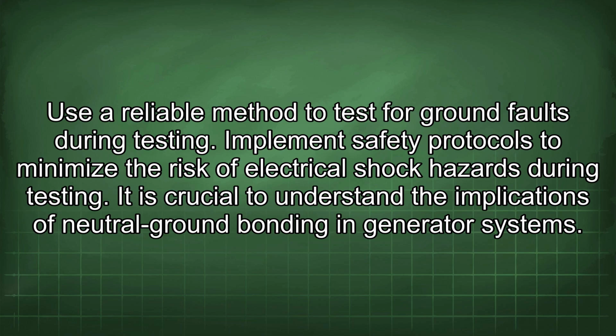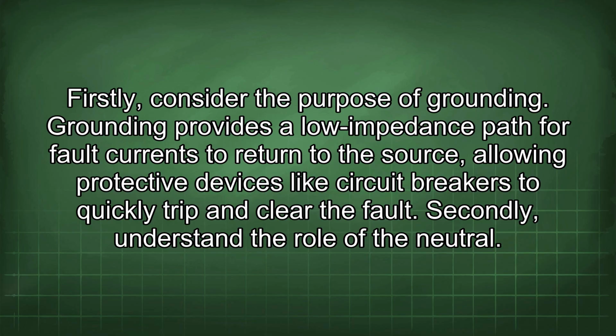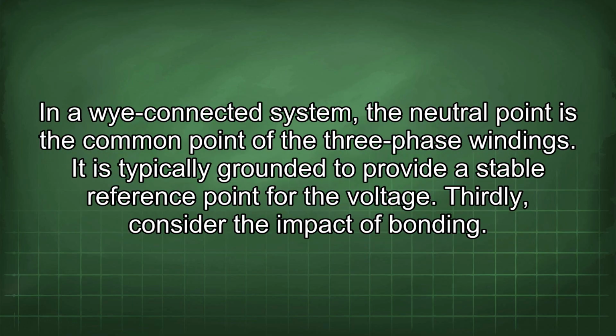It is crucial to understand the implications of neutral ground bonding in generator systems. Firstly, consider the purpose of grounding. Grounding provides a low impedance path for fault currents to return to the source, allowing protective devices like circuit breakers to quickly trip and clear the fault. Secondly, understand the role of the neutral. In a Y-connected system, the neutral point is the common point of the three-phase windings. It is typically grounded to provide a stable reference point for the voltage.